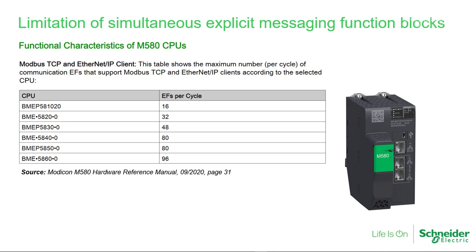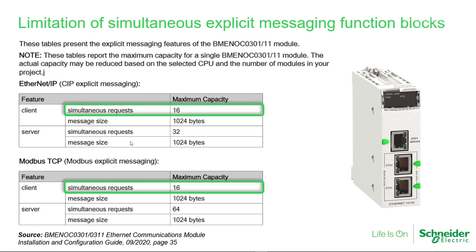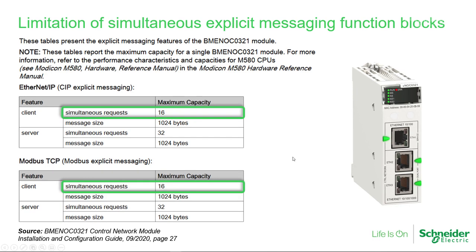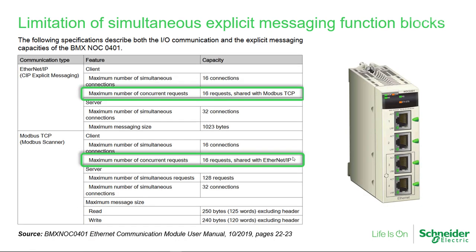The maximum number of simultaneous explicit messaging function blocks is documented in the user guides for each processor and Ethernet communication module. For M580 CPUs, it varies from 16 to 96 depending on the CPU model. For the BME NOC 301 or 311, and also the BME NOC 321 module, the maximum is 16. The BMX NOC 0401 module for the M340 PLC also has a maximum of 16 simultaneous requests shared between Modbus TCP and Ethernet IP.